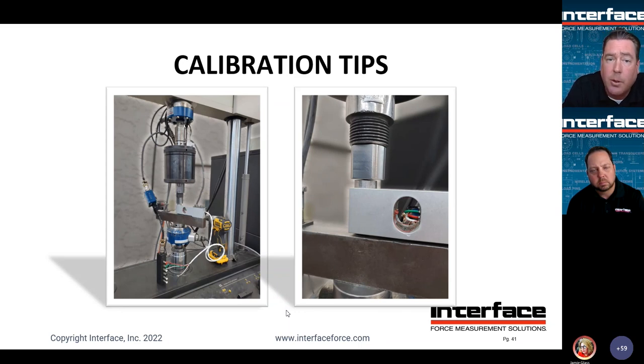And the example on the right shows the loading point of the SSB. We have a spherical adapter that's been placed on the SSB, again, looking for that single point of contact. And then we have a flat thread adapter that's actually applying the calibration load to the end of the beam. And then that metal mounting surface is designed to essentially not deflect appreciably under that load. So a stiff enough surface suitable to not deflect under those calibration loads.